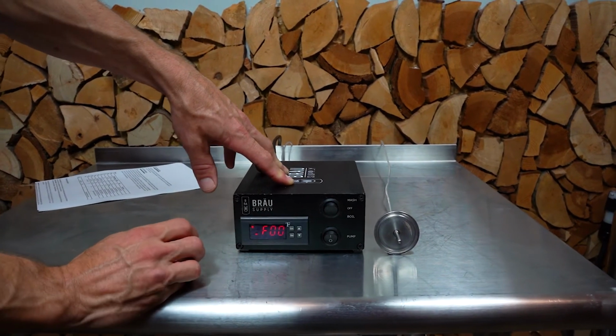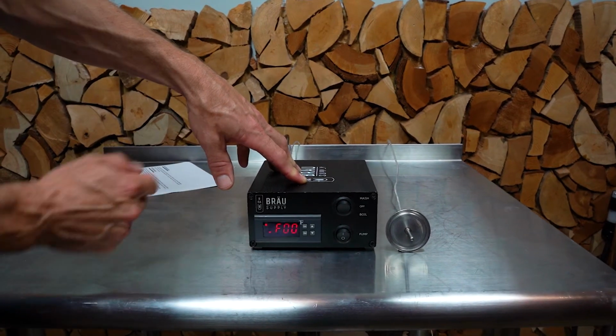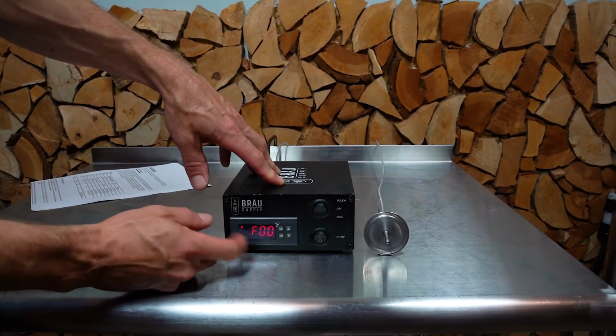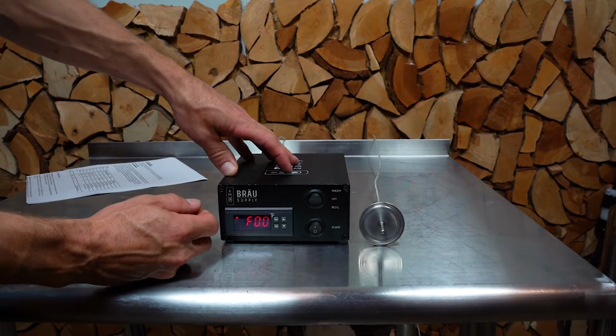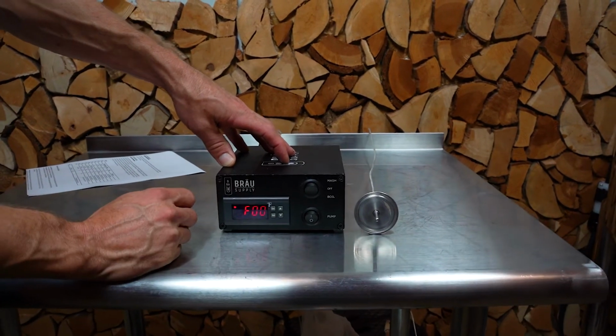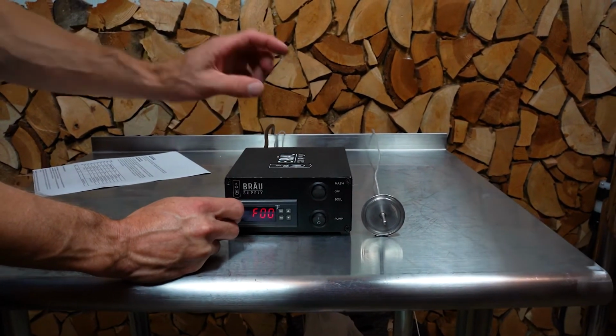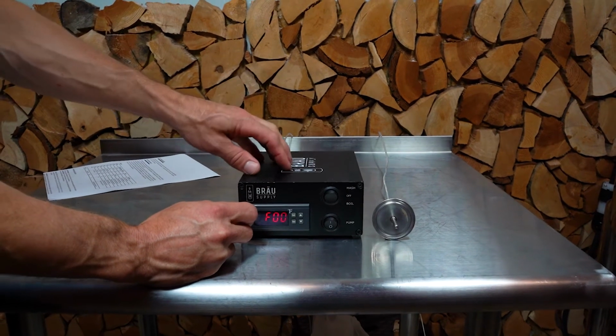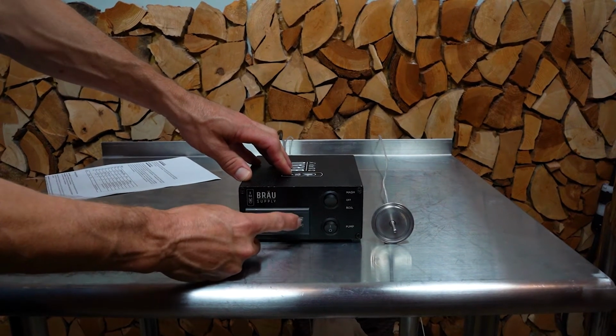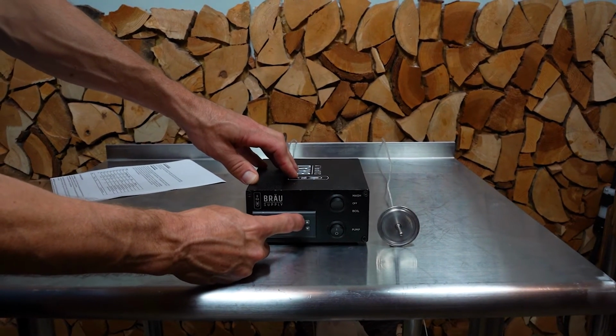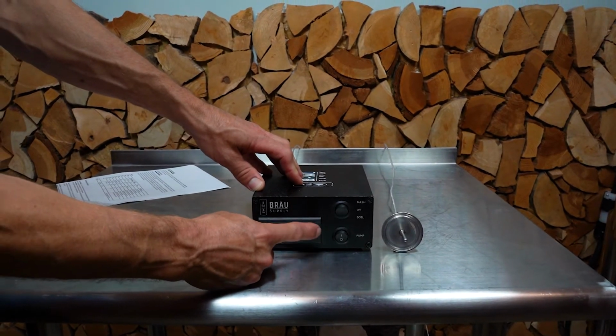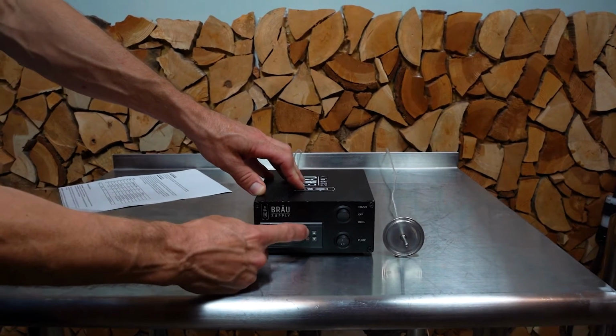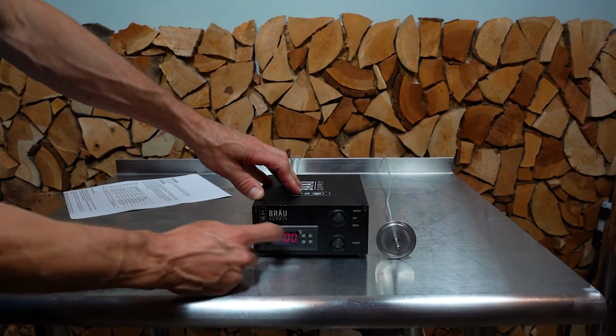And the cooling differential essentially is, if it's 1 degree, it means that if it deviates 1 degree off your set temperature, it'll enact the cooling solenoid, or it'll enact the cooling output, and that only affects the cooling outlet on the back of the controller. You press set again. Set brings you in. Set brings you out. Now it's F00.